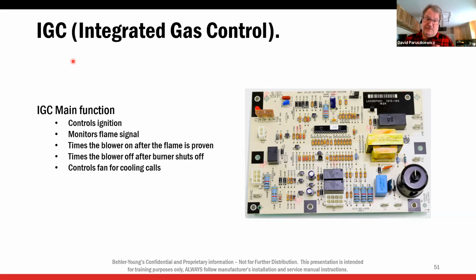So this is the other board, all right? We have the terminal board, which is basically a junction point, and then we have the gas control board. This board here has not changed much over the years. There's a fuse on it. There's a light we're going to talk about in a minute. This handles ignition. It handles flame proving, flame monitoring. This is what these two relays here are: your high and low speed blower. This is what turns the blower on for heating and cooling. So this is what's sending the signal to that little fan relay board that's coming off the IGC.